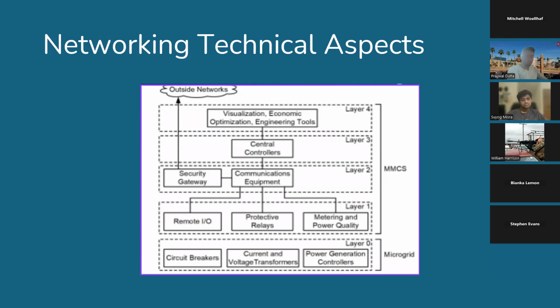Layer 2 in this architecture is where the communication network lives, including gateways and switches. This layer ensures seamless data flow and time synchronization, and it also ensures secure control commands across the system. Layer 3 is central control, where our microgrid controller runs automation logic. It's here that all of the protection and automation rules are processed, often in real time, to keep the system safe and efficient.